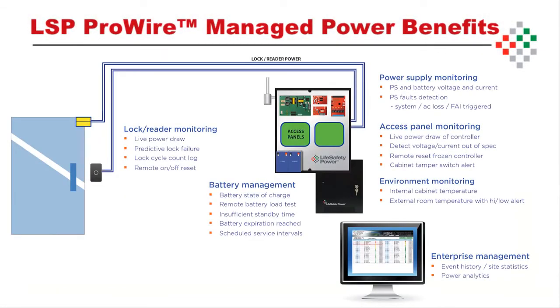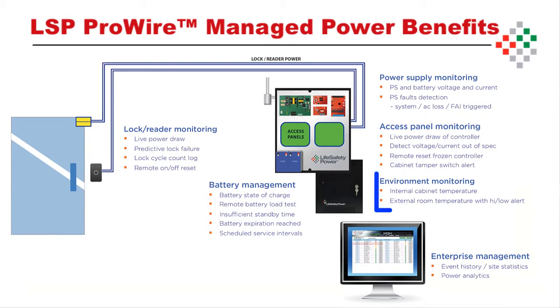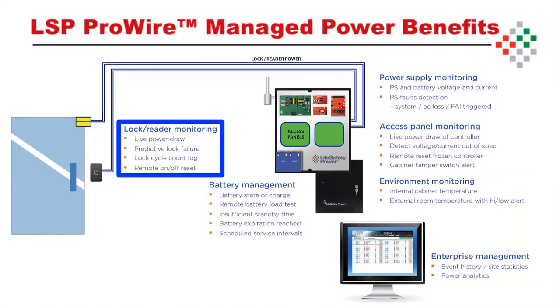More than just a power supply, LSP provides key information on system health in every area. The power source may be continually monitored for voltage, current, and fault condition. The access boards may be monitored for live and historical power draw, applied voltage and current values, tamper switch condition, and may be remotely reset. External room temperature and internal enclosure temperature are monitored for operation within user-defined limits, and partial or complete coil failures within the lock are detected immediately.